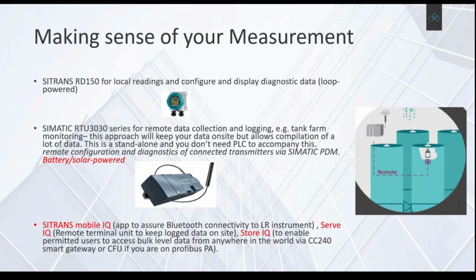There are programming functions on the RTU. If you want to record over a certain interval, say 5 hours every 2 weeks, you can set that and it will report back, throttling back its use of the LR100 so it only takes readings at those times. The LR100 could even be loop powered through this, only activating when the RTU wakes itself up to record, then switching off when programmed. There is programming on board, and it's intuitive, not like reading hieroglyphics.